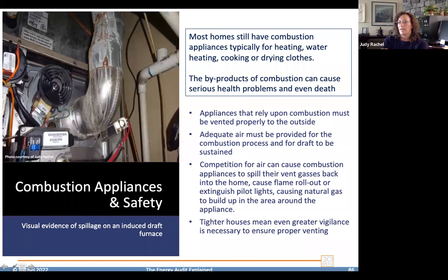So we need to do visual evaluations, and we get all kinds of visual clues from our combustion appliances. We can see that combustion gases are actually leaking out of this induced draft system. A lot of people are under the impression that induced draft vent systems don't leak. And this tells us that, to the contrary, they absolutely do. This is the combustion gases having condensed on the metal and dripped down.